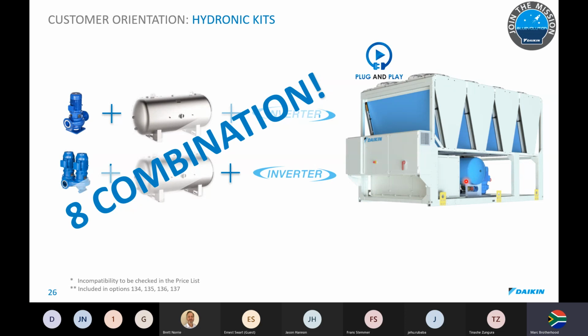Depending on the chiller size though, as a rule of thumb, normally 5 to 8 liters of water is needed. Sorry, 5 to 8 liters of water minimum per 1 kilowatt of cooling. So if you don't have enough water pipe or water reticulation in your system, you can have one of these buffer tanks put in to absorb the buffer. If not, you can put an external storage tank. We offer up to 1,000-liter external storage tanks, which come insulated as well.